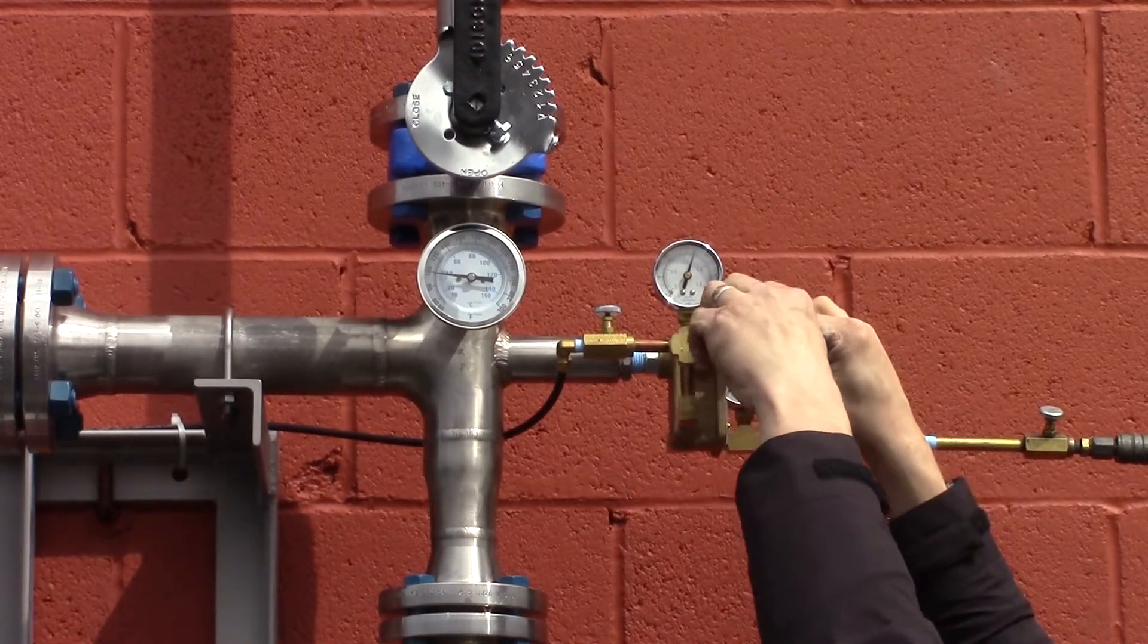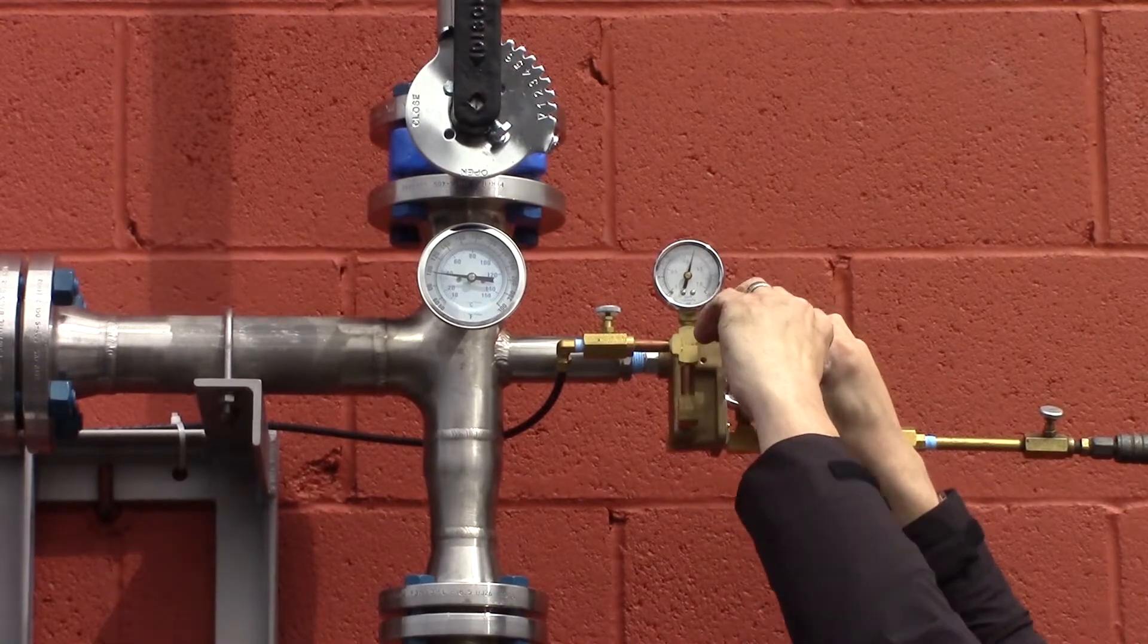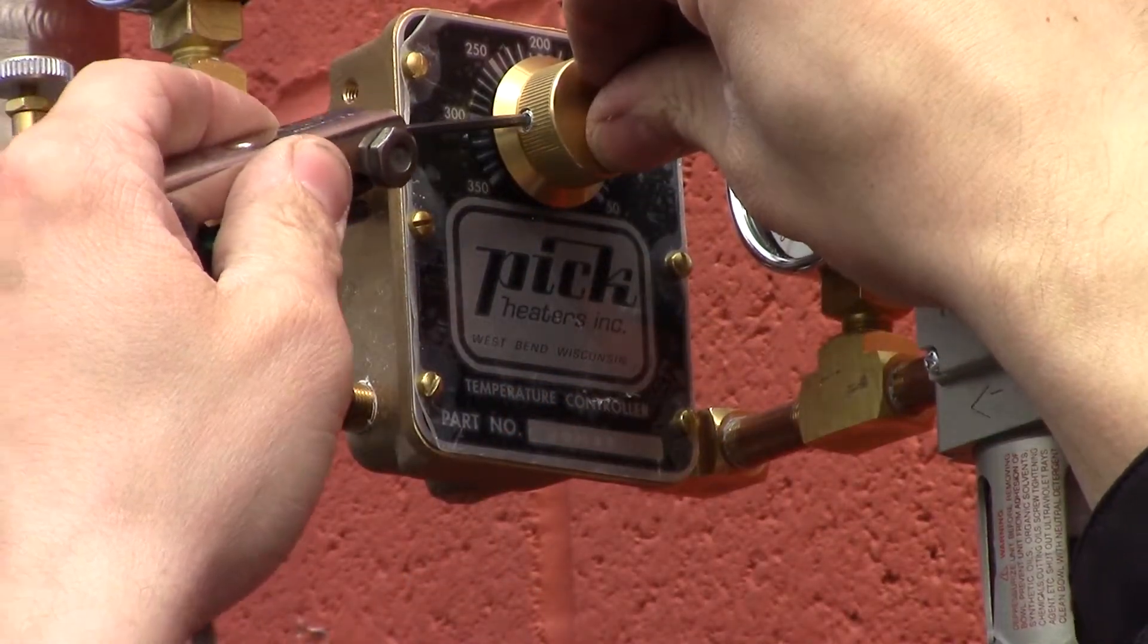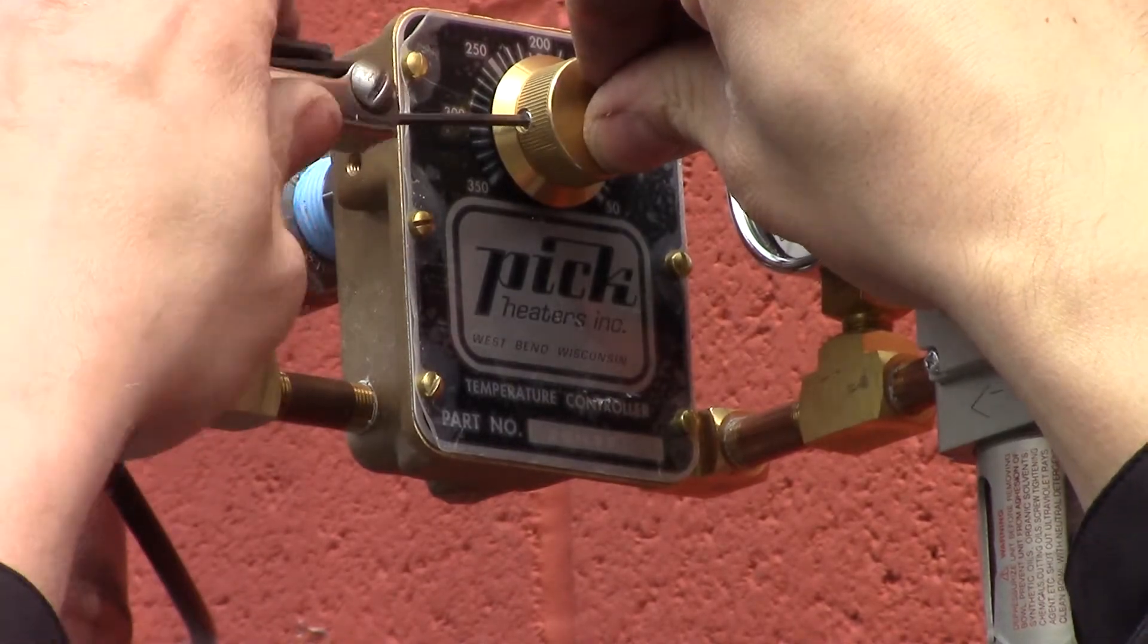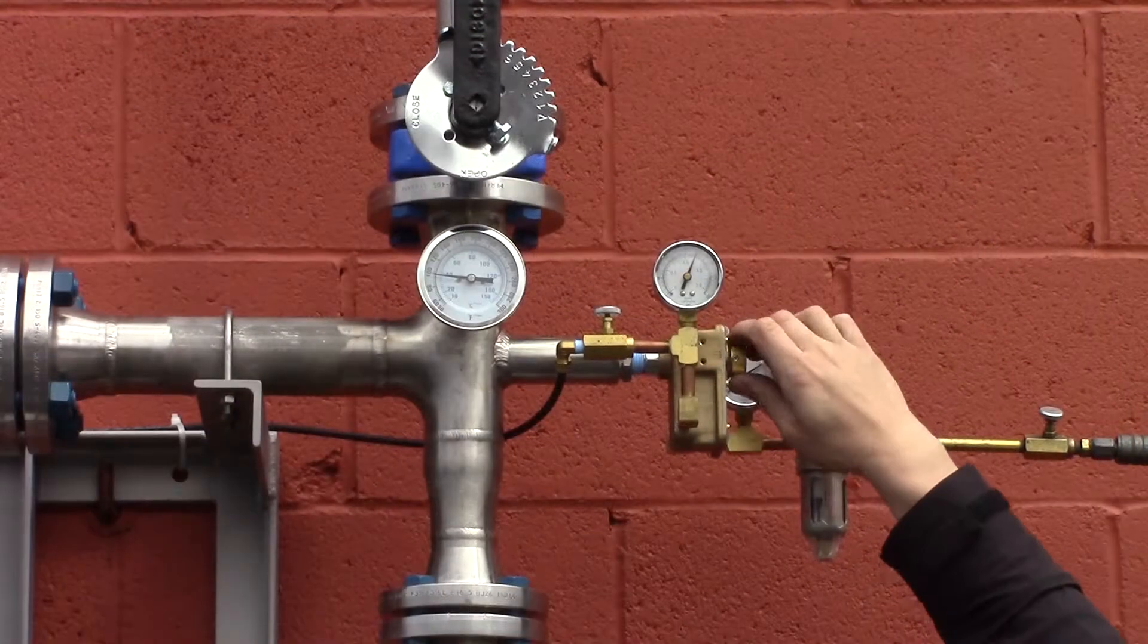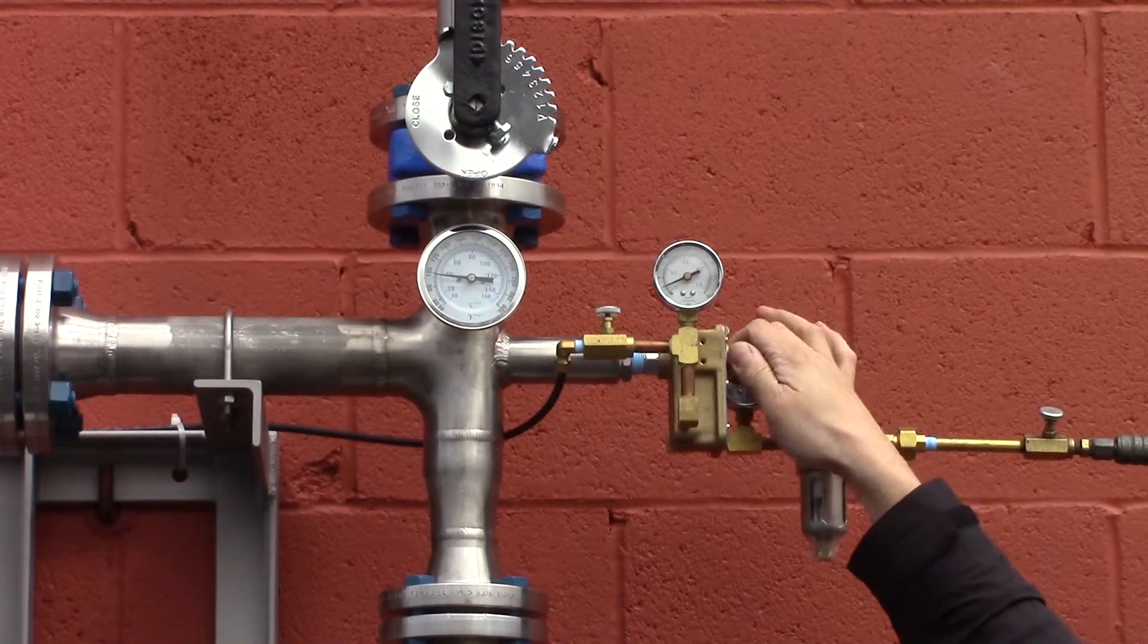Then firmly tighten the set screw in the knob. Verify the knob and dial thermometer read the same temperature. Rotate the temperature controller knob clockwise to lower the temperature set point and shut down the pick heater.